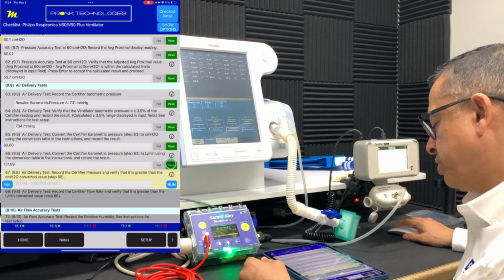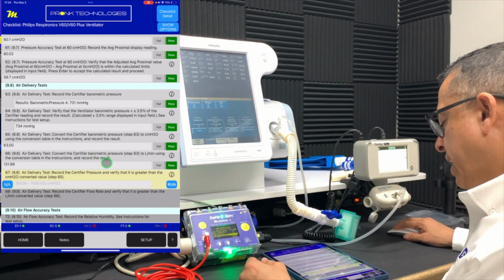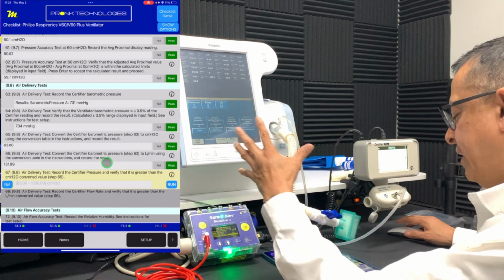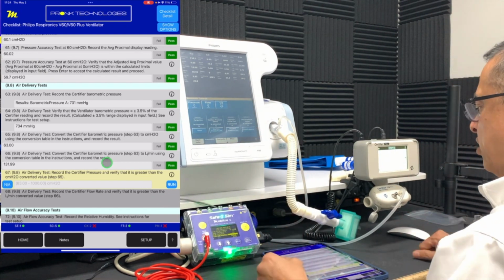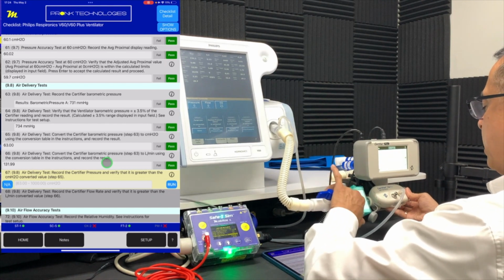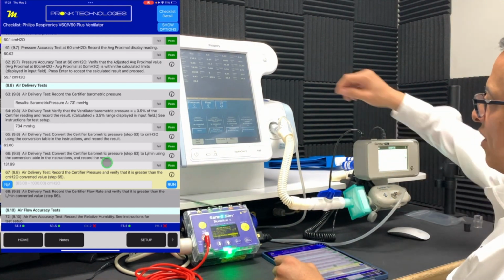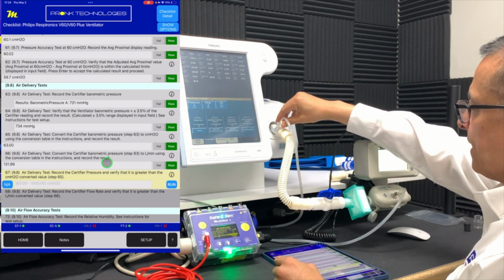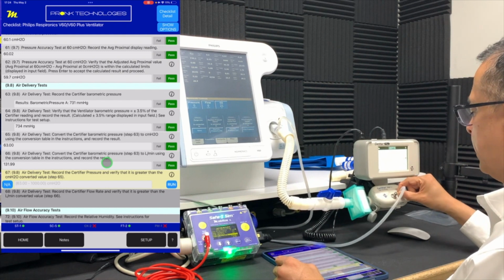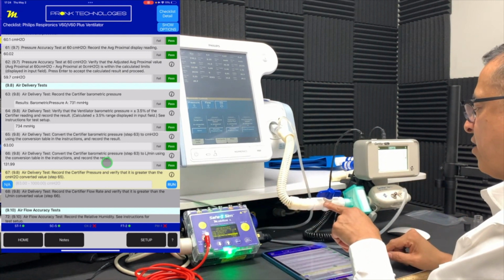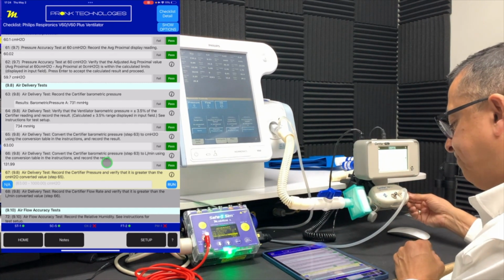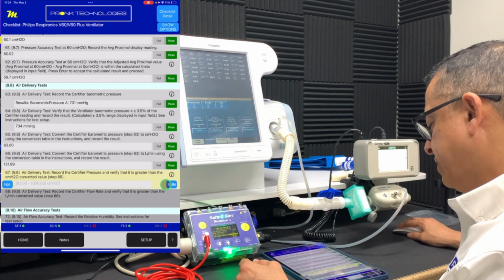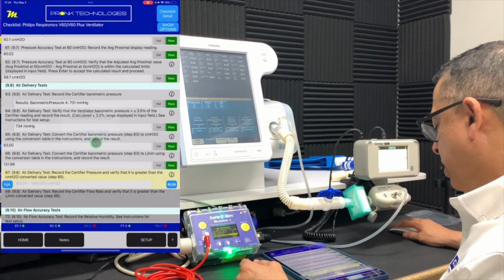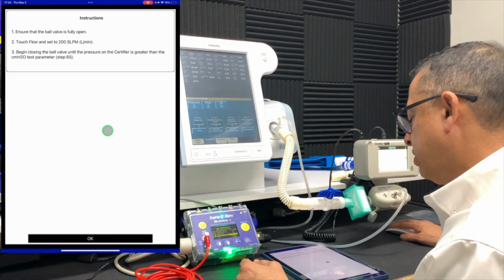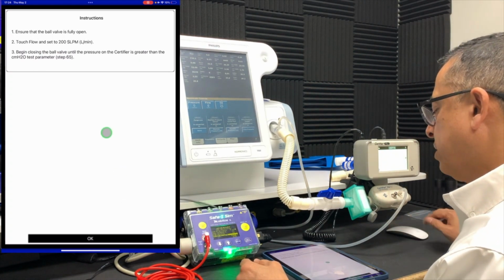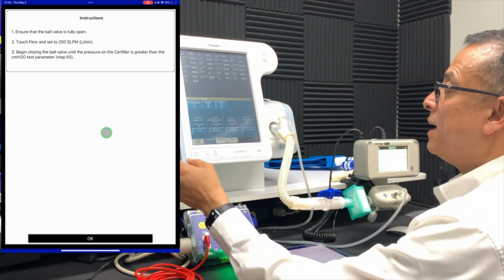It'll be important for the subsequent measurements we're going to make. So now we want to confirm that the certifier pressure is higher than the centimeters of water converted value. But we need to make sure we can set up the test, the certifier to perform this test, which involves connecting our pickoff port over here so we can measure into our pressure port in the certifier flow meter. We need to connect our flow valve here as well with the filter and make sure we leave the output open. So now we want to go ahead and run that test and make sure we set it up properly. We want to go ahead and confirm that we set this up properly, and we do that by set the flow to 200 liters per minute. And so I want to go ahead and do that.